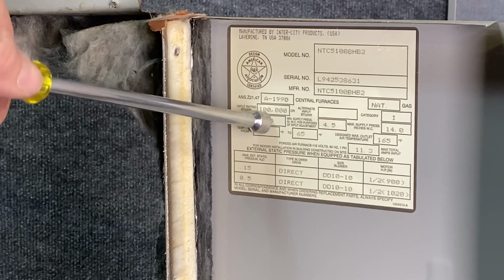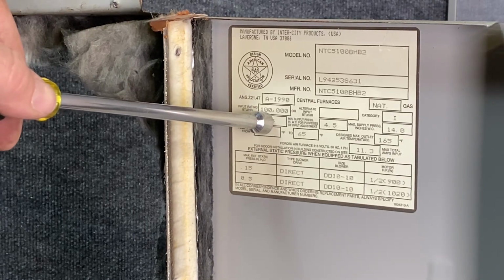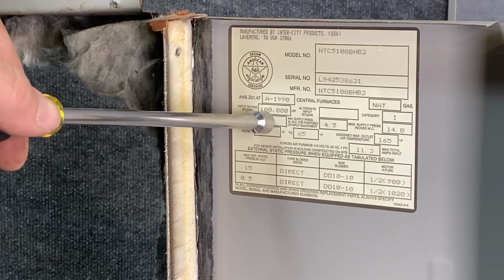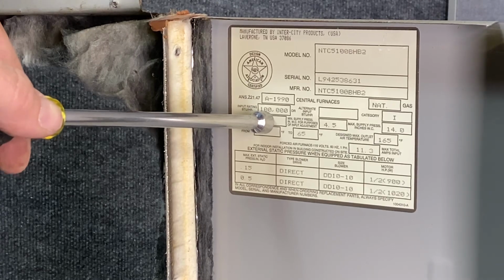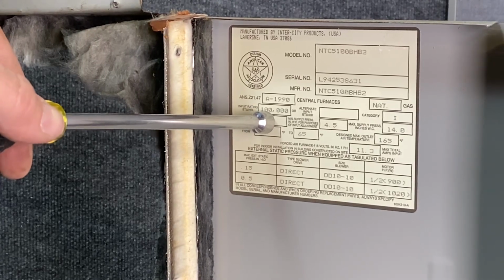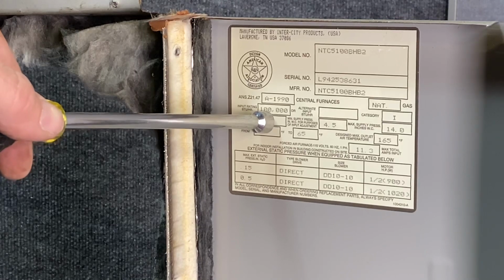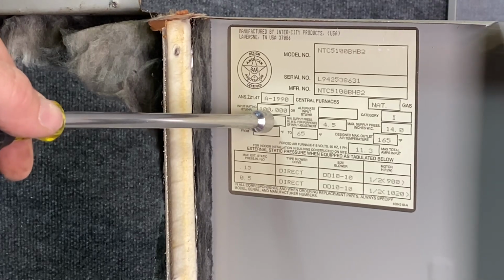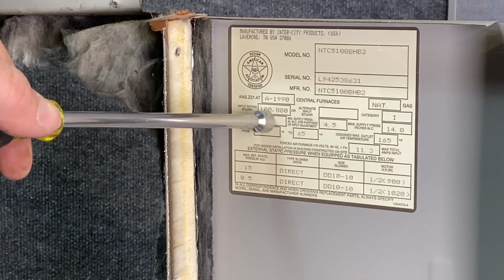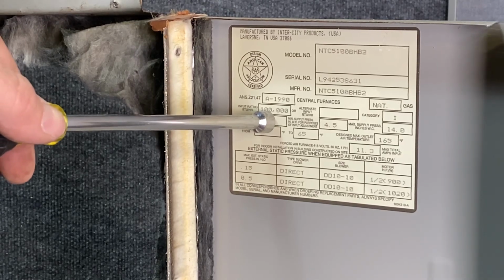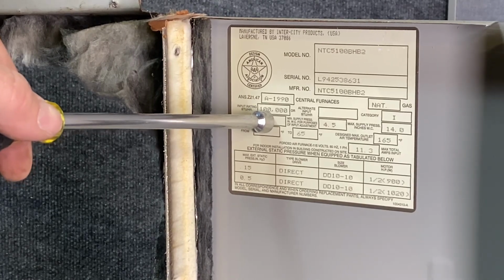It's designed for 100,000 BTUs per hour input rating. That's how we use to size the gas piping. However, it's an 80% furnace, so it's actually an 80,000 BTU output. So you always want to make sure you take your efficiency into account when you're sizing the output. If this furnace was replacing a less efficiency unit, you could easily oversize. The new furnace needs to be matched with its output as well.